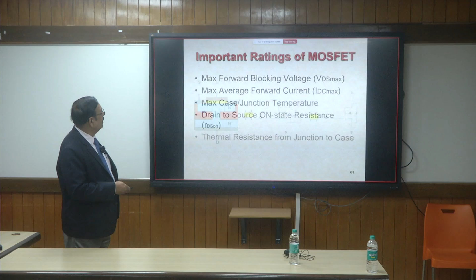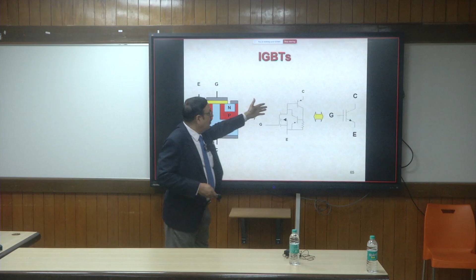IGBTs are similar - they have two parasitic bipolar transistors, creating a parasitic SCR structure. Modern technology has drastically reduced this parasitic effect, but it's still present, and at high dv/dt across the IGBT it may latch up, causing loss of control. High means more than about 3 to 4 kilovolts per microsecond; below that, you don't have a problem.